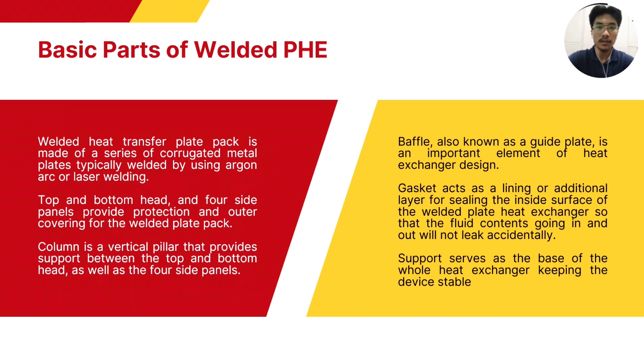Again, the gaskets on this plate pack are non-existent anymore because the plates are welded, and also the gaskets are just limiting the operating potential of most types of PHE or plate heat exchanger. So by having gaskets, the operating conditions are limited to up to 180 degrees Celsius in terms of temperature and up to 25 bar in terms of pressure. By removing those gaskets entirely, the operating conditions of a welded PHE can exceed those limitations. So it can go beyond 180 degrees Celsius and above 25 bar.